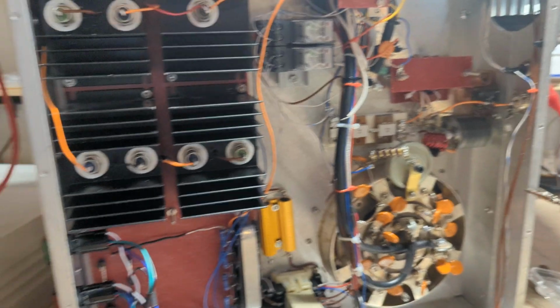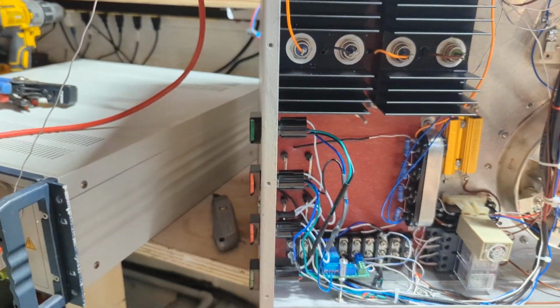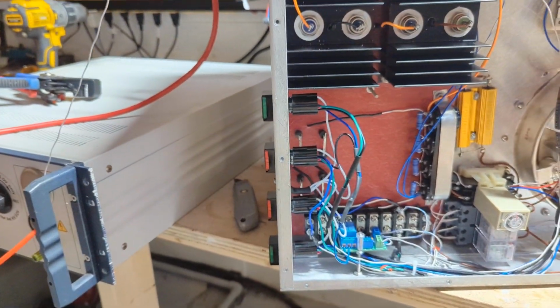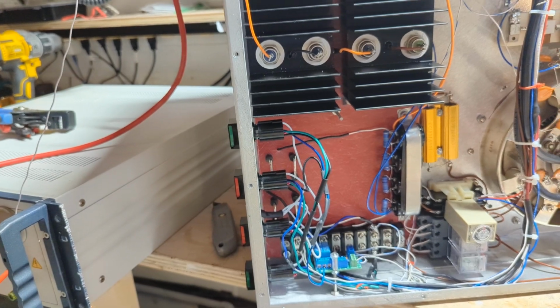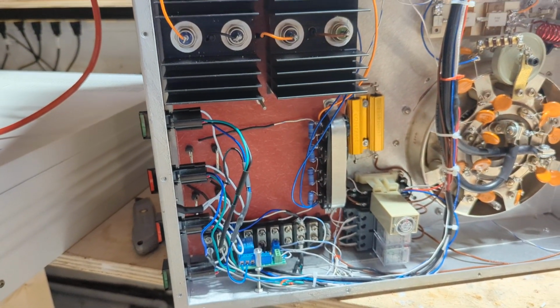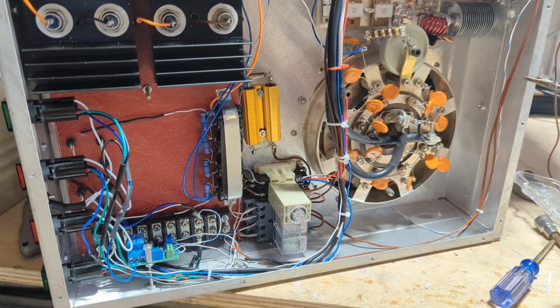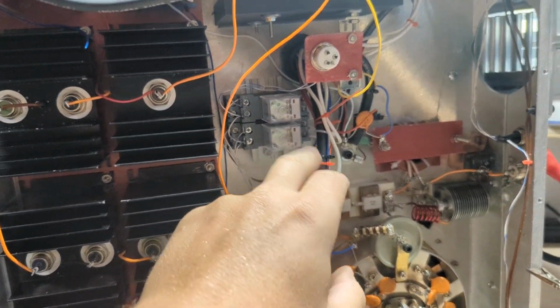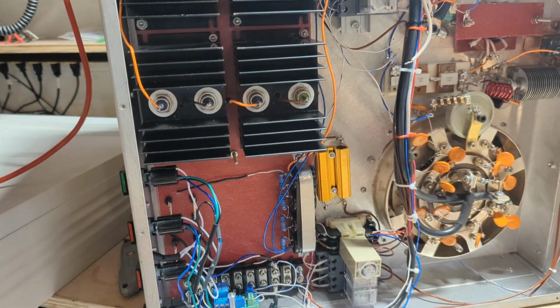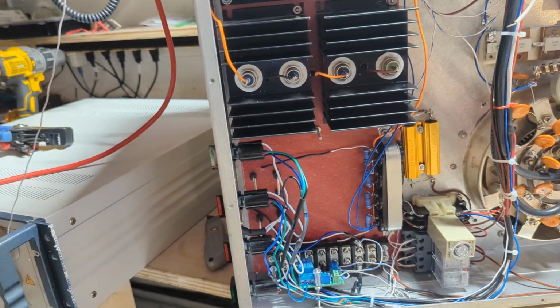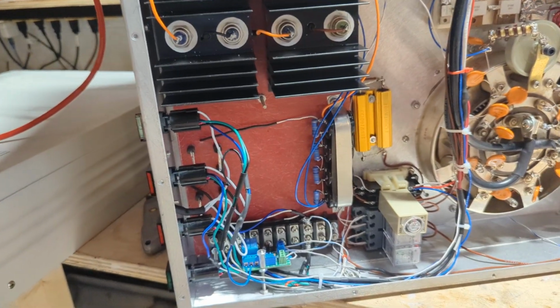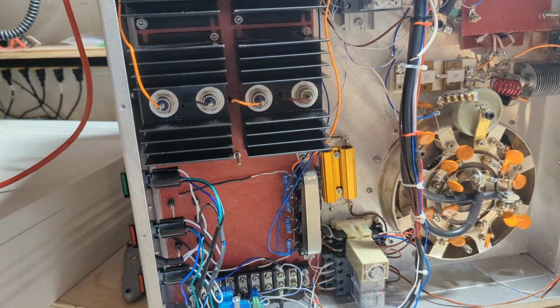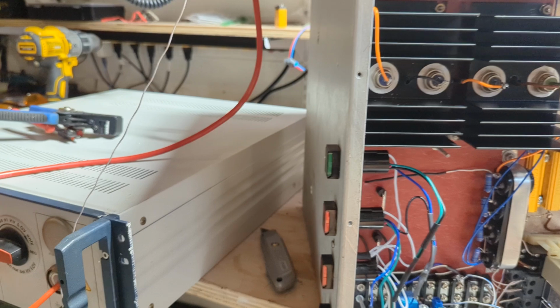So you come up to this box and it's totally cold, it's not running. Obviously you'd have to turn on - my power supply is separate, so you have to engage your power supply, but the power supply is not actually turned on, it's turned on remotely, where one of these relays will remotely turn on the power supply. You put your power supply in standby, it's running, the fans are running in the power supply, but the power supply does not actually provide any high voltage until you ask for it.